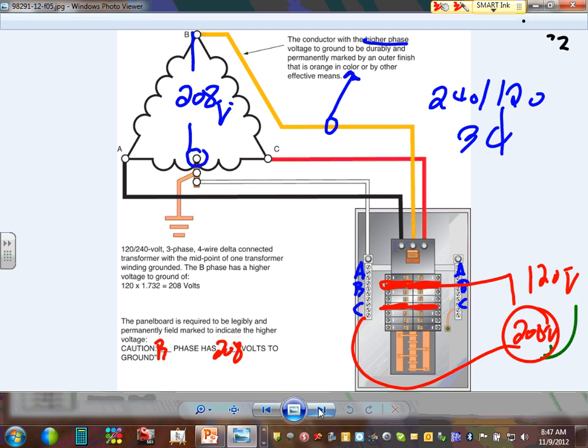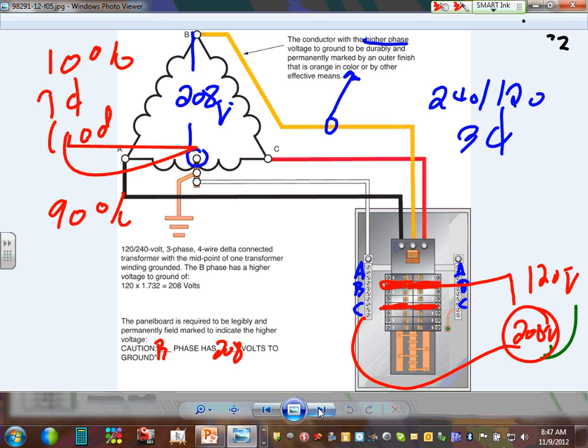Where would you use a system like this? Personally, well houses for cities, lift stations for cities are notoriously famous for having them. I always tell people, in a place where 10% is single phase load and 90% three phase load. A place where single phase is only 10% of your load, that could be an application, and the system is 240.